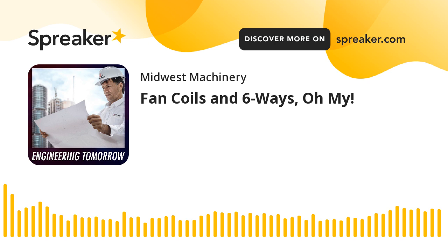VAV products do not normally have a fan, at least the standalone units. We do offer series and parallel flow VAV products that are meant to work in conjunction with air handling units. And they do offer heating and cooling. I kind of refer to them as a poor man's fan coil, but it's a way of moving fresh air in, while making sure you pre-treat that air before you dump it into the comfort cool area. But yes, you do have parallel flow and series flow.